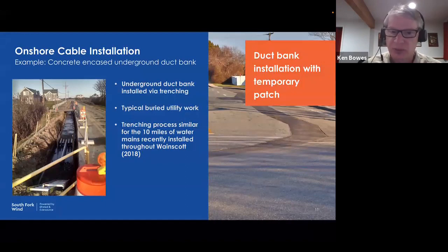These vaults are about 26 feet long by 10 by 8, so still like a large minibus being buried. Those are about every 2,000 feet. Our initial design shows we're going to use 10 of those along the route, which includes the 2 miles of town roads and the 2 miles along the LIRR. So about 6 vaults in the town roads and then 4 along that straight shot section to the substation on Cove Hollow.